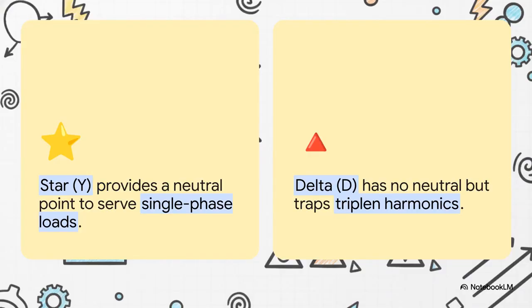Okay, let's zoom in on the copper wiring itself. When connecting these three phases, engineers essentially have two main choices. First, you've got the star, or Y connection, which connects all three windings to a common neutral point. This is fantastic because it gives you a usable neutral for grounding, which lets you serve single-phase loads easily. On the other hand, you have the delta connection, which forms a closed triangle. Now, it has no neutral, but it handles unbalanced loads so much more gracefully. And crucially, it traps those unwanted internal triplen harmonics right inside that closed loop, instead of letting them leak out onto the main power line.